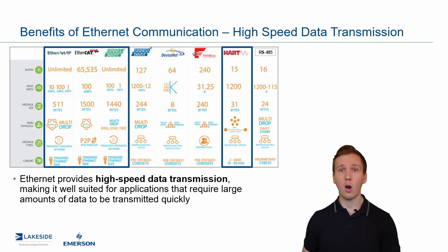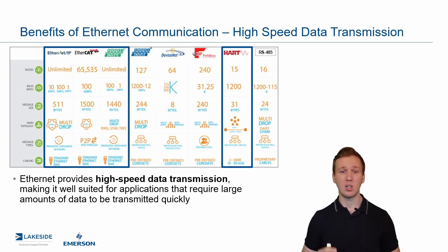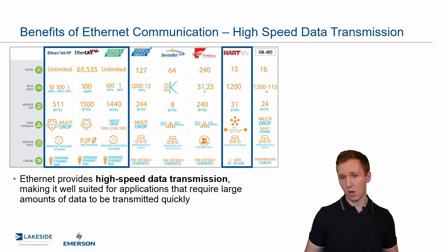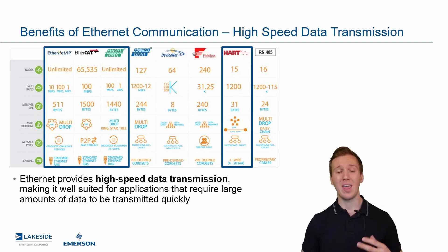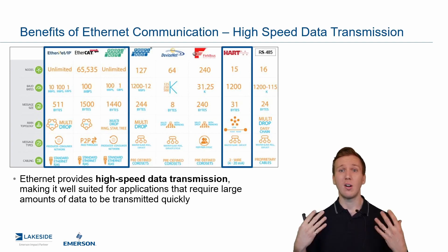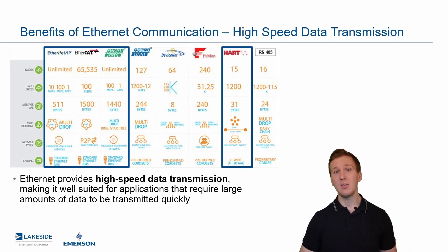Now, many of us are very familiar with HART. HART is a very common protocol that we see across many different industries. And if we look at the baud rates, you can see there is a significant speed reduction when we utilize HART. Anybody who's ever connected to a device and communicated via HART, especially as we transmit a ton of data, is going to notice how slow that is. This is a limitation of the protocol. So for any devices where there is a ton of data to be transferred — Coriolis sensors, analyzers, radars — Ethernet actually has a big benefit compared to HART protocol.